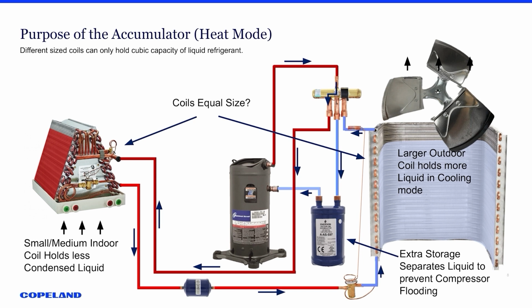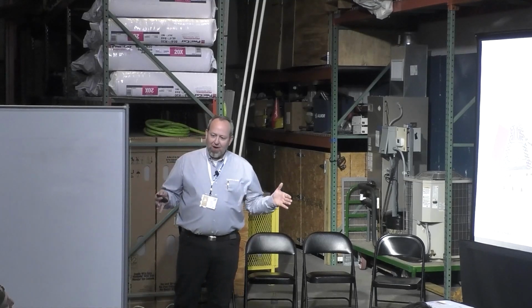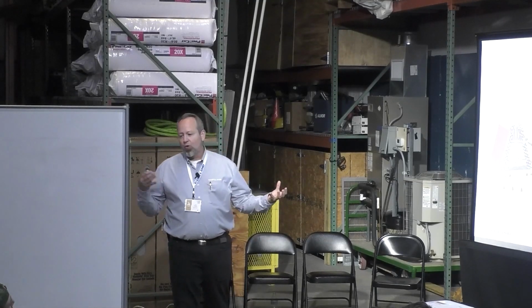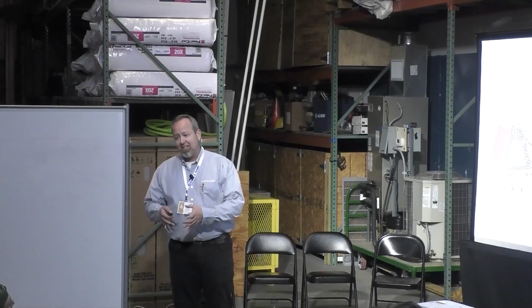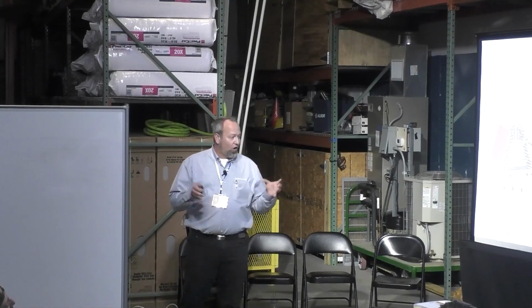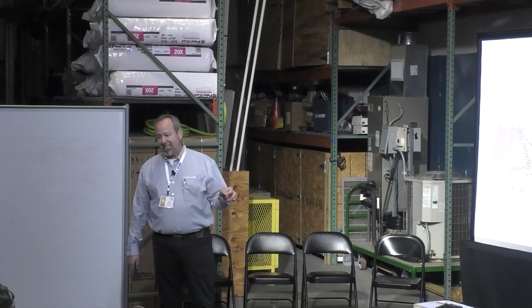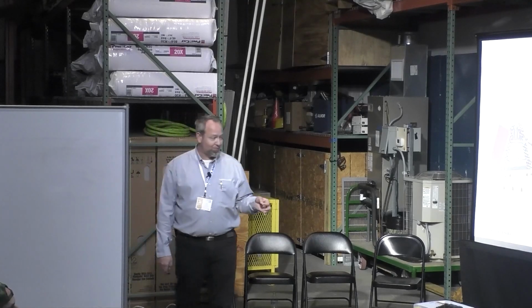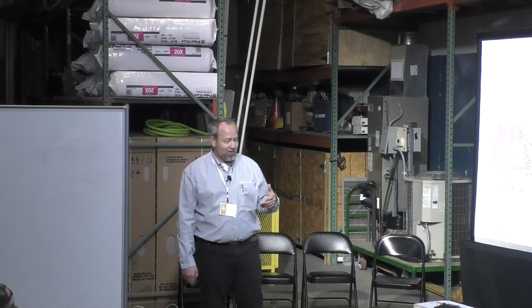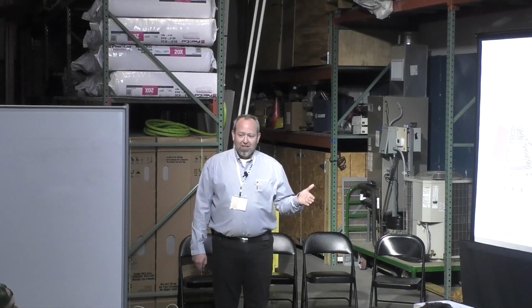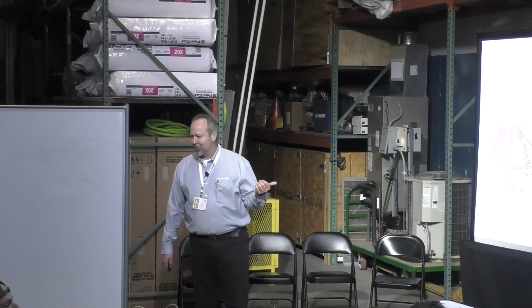I think we've already gone through this. Really, the purpose of that is to store that extra refrigerant, to be able to hold that extra capacity designed by the manufacturer when they designed the indoor coil, the outdoor coil, and the size of that accumulator. And so all three of those things are designed together when they design these systems. And to be able to put a system in, I'm going to go ahead and jump to it because I can talk to it here as well.